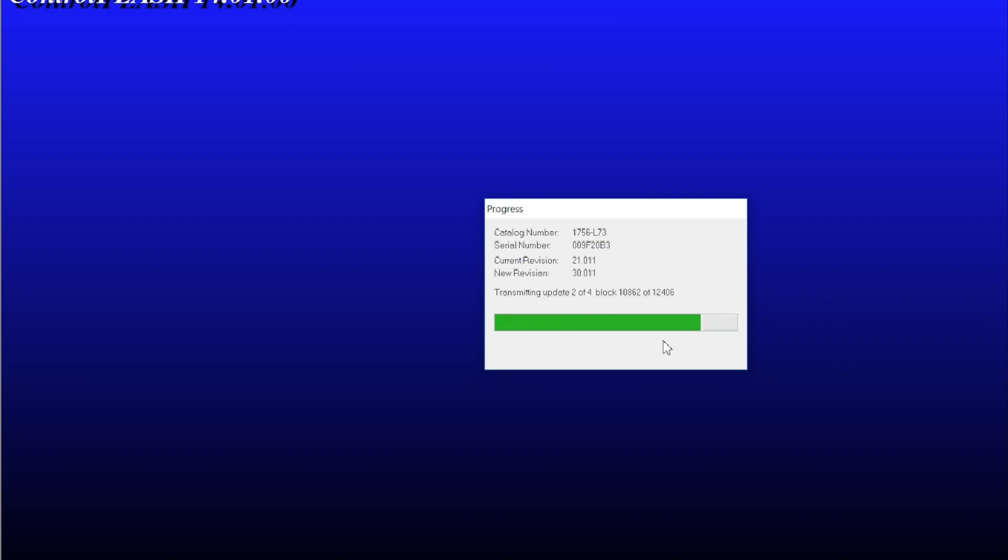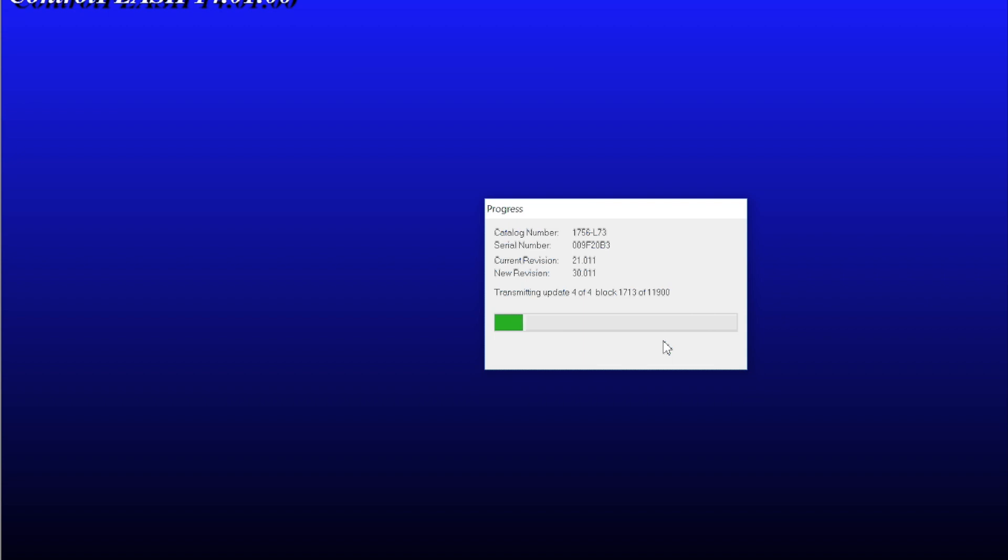Also, as is the case for all Studio 5000 firmware versions, you have to purchase the firmware that you want to install. Unless you have some type of license agreement with Rockwell or already have the version, make sure that you have the licensing and the rights to the firmware you want to install available in your facility. That's why it's a great idea to standardize in a particular firmware package that allows you to have them all in the same version. And have one version installed and licensed for all your technicians and engineers that might be programming or accessing your processor.